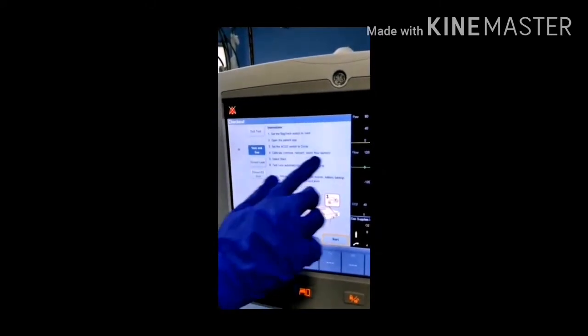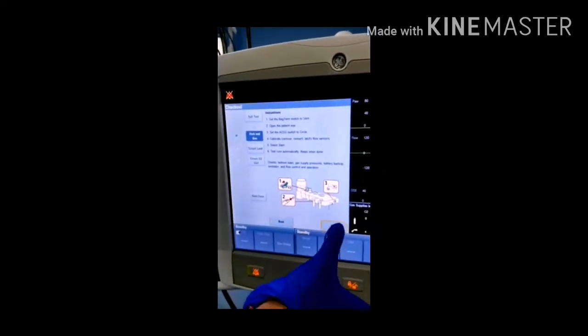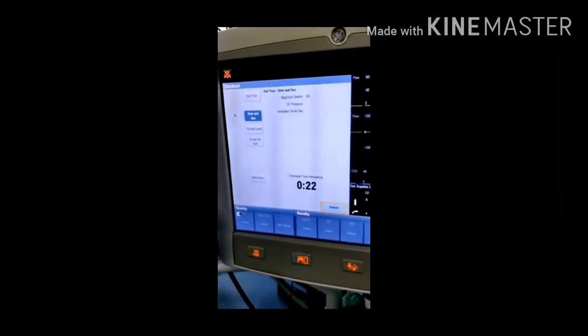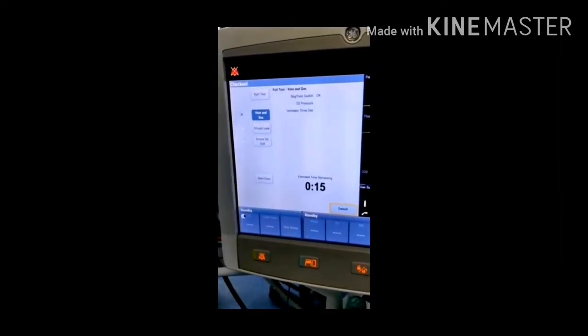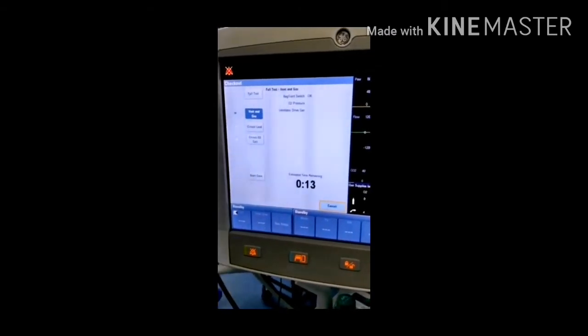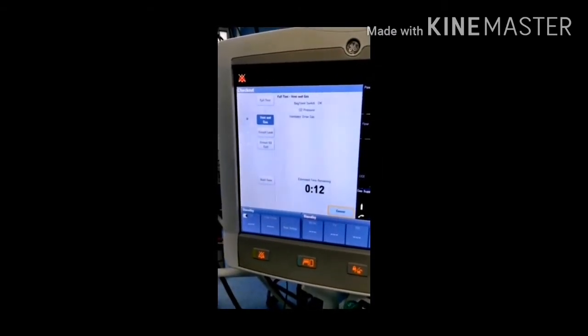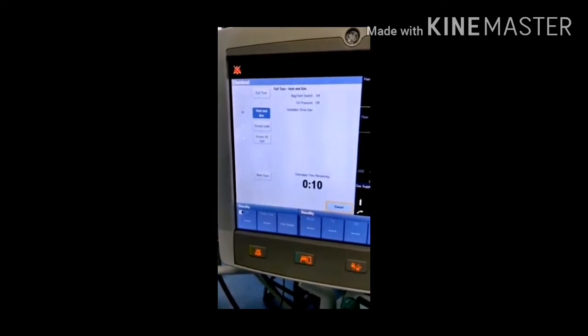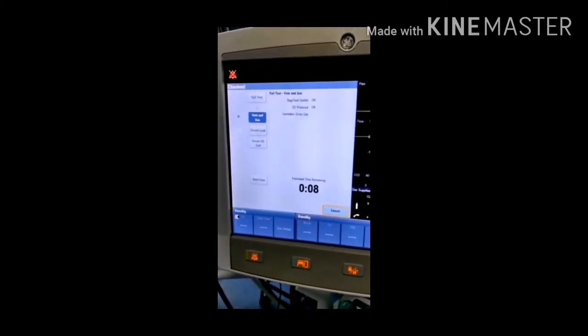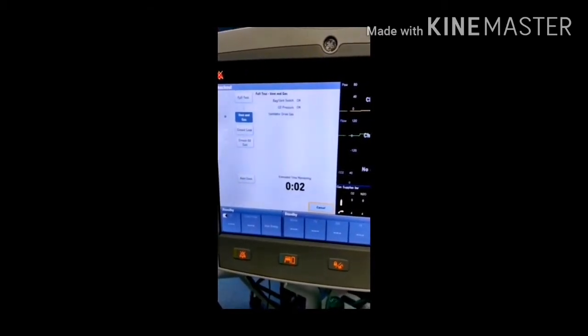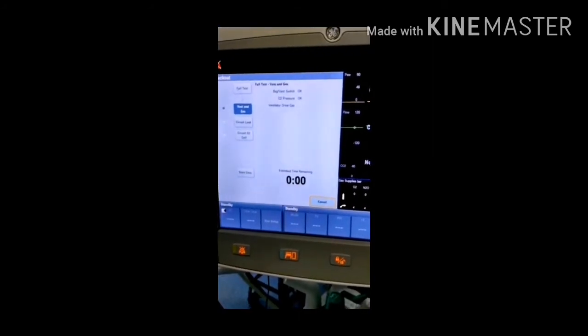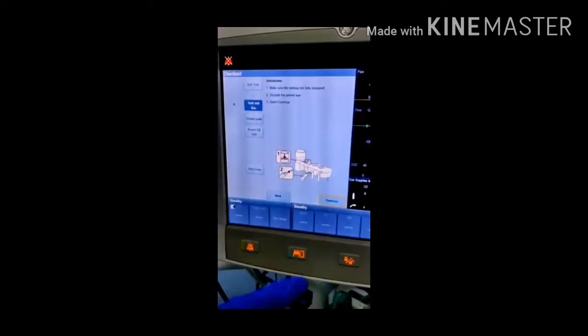To calibrate the flow sensors, as we had removed and reconnected them, we have already done that. Just press the start button. It shows switches, pressures and the drive gas, whether there is any leakage or the pressures are okay. It is being measured. Since all tests have passed, it has moved ahead. So make sure the bellows are fully collapsed. As you can see, the bellows are at the bottom level.